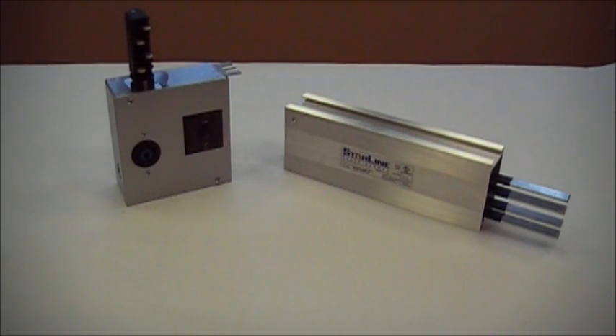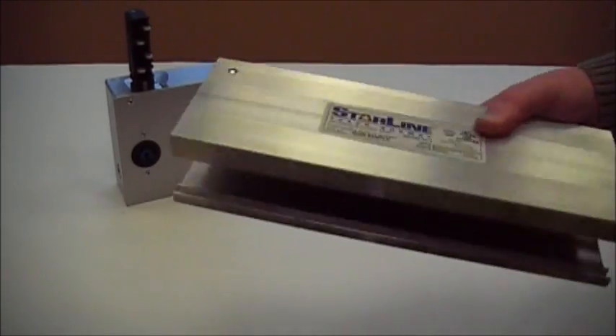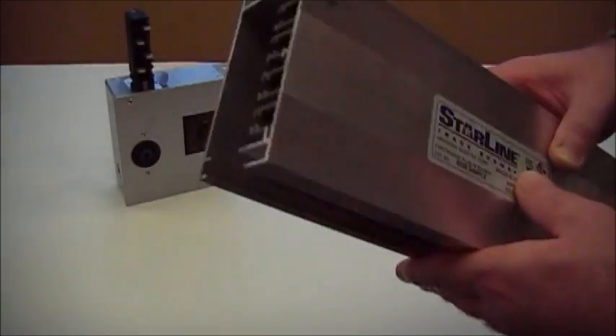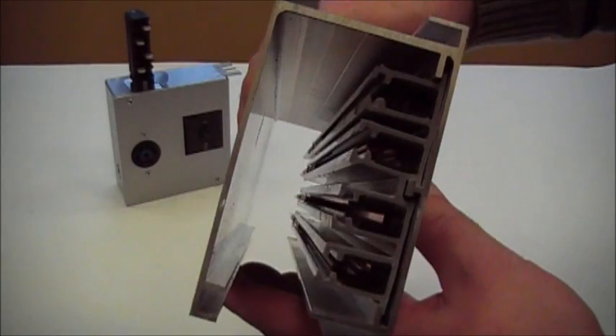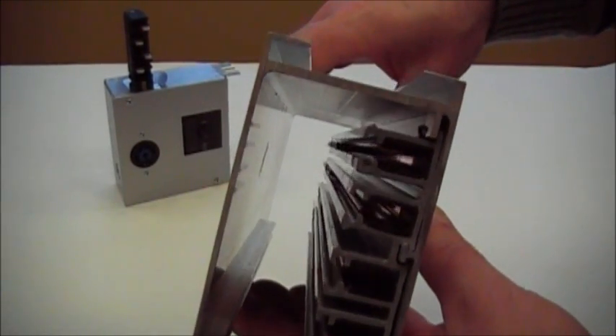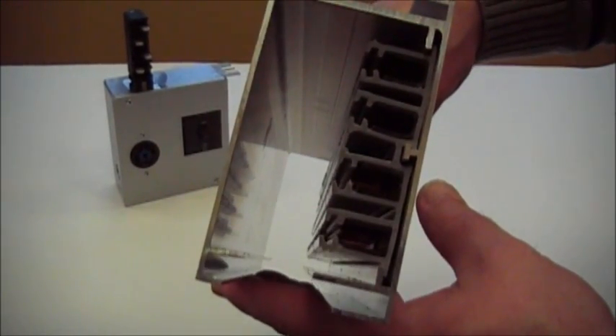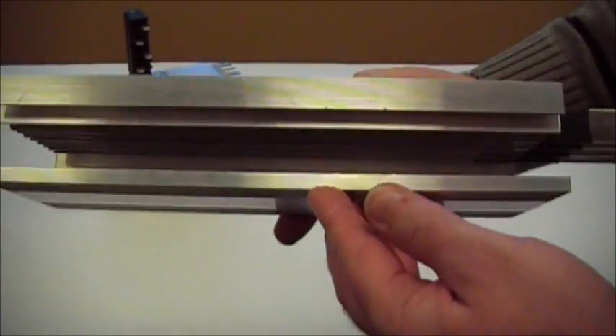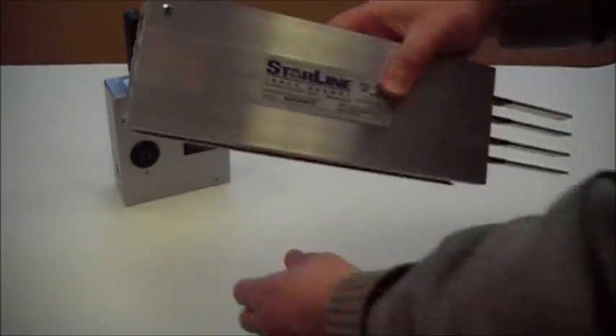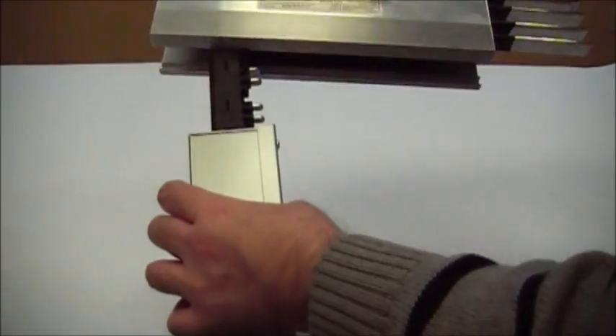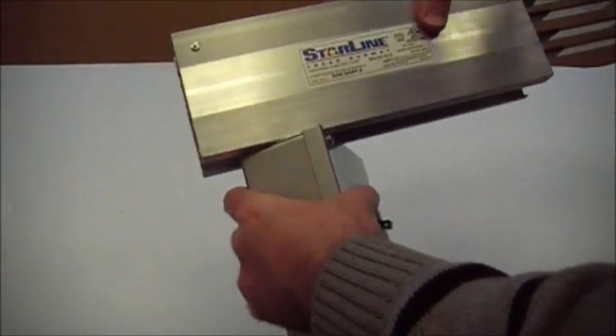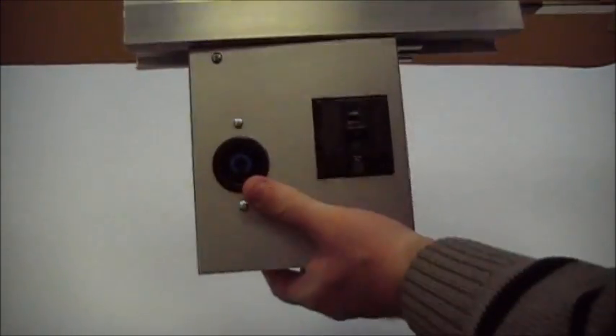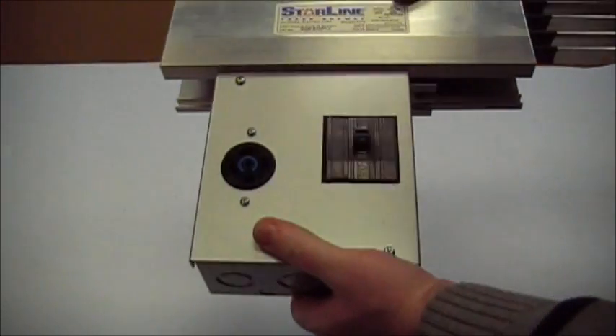And we're showing the Starline track busway and the plug-in module that goes into it. The Starline track busway has a continuous access slot, aluminum housing, and copper conductors. The conductors are roll formed to accept the paddle, and the housing is also rated finger safe from UL. So we'll install a plug-in module into the housing now. You simply insert the paddle into the housing, turn it 90 degrees, which makes connections into the busway.